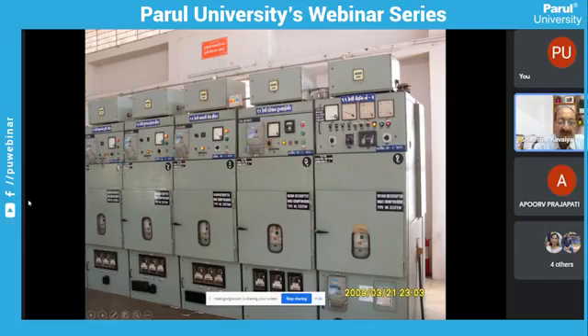So see, from the 66 to 11 kV transformer, the power will come to 11 kV main 1 and 11 kV main 2. If there is a fault in this bus, see, there is a bus here inside, on the back side. You can't see it here, but there is a bus inside this. So if there is some problem in this breaker, it gets fired and this 11 kV main 2 will trip. But in that case, supply will be resumed from 11 kV main number 1. So this is something basic.